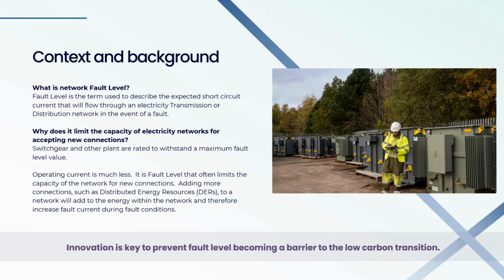The difficult thing about measuring fault level is that we're trying to measure something that's not always there. Fault current is only normally there in the event of a fault. We can't go around the network throwing faults just to see what the fault current is. So we've had to approach this using some fairly innovative approaches. In fact, when the project very first started, even predating my time with it, it was seen as something that was potentially impossible to do. But as we'll go through in this presentation, you'll see how we've been able to achieve it. If we just move to the next slide, please.